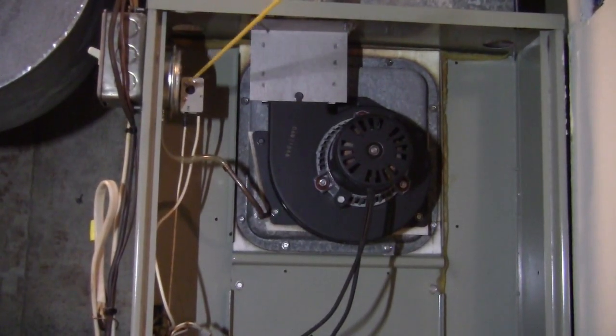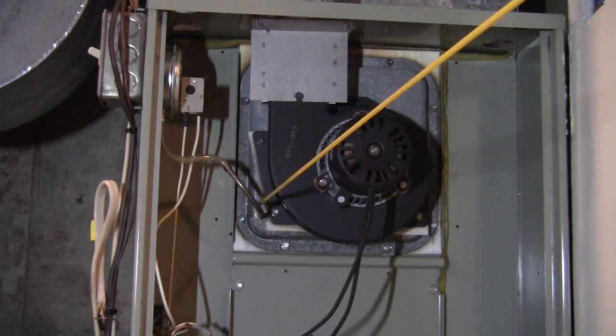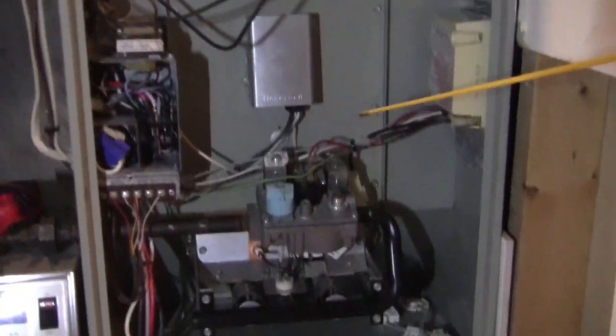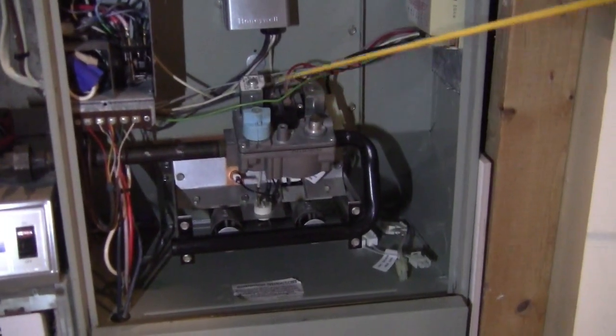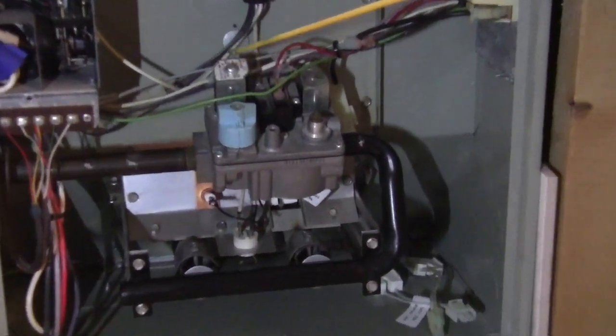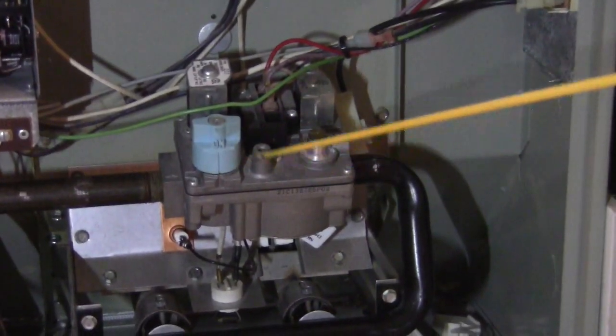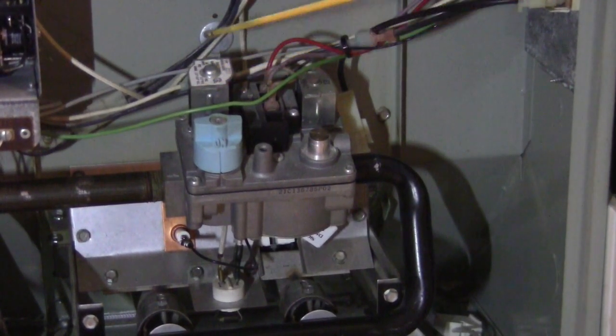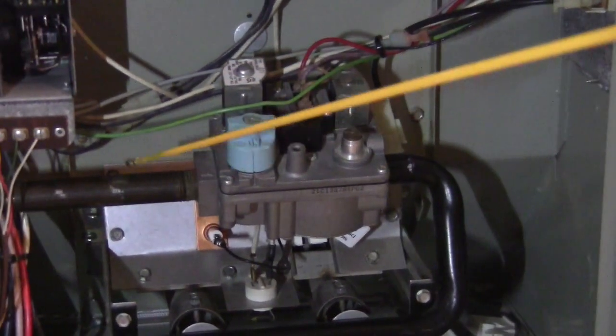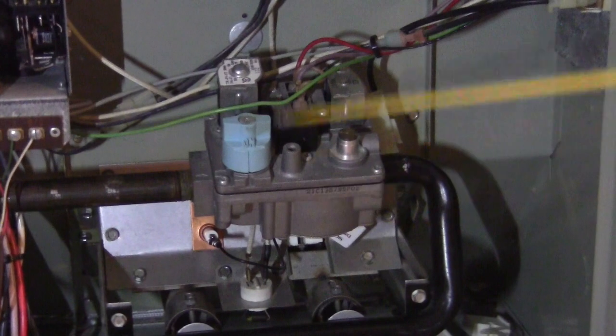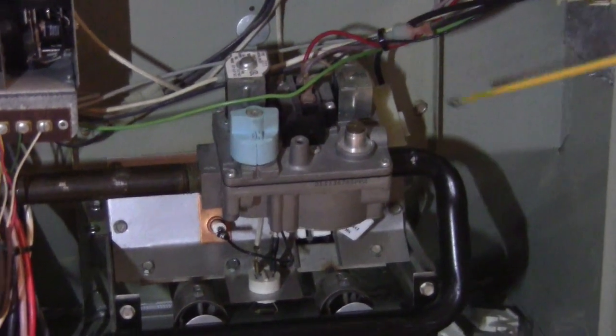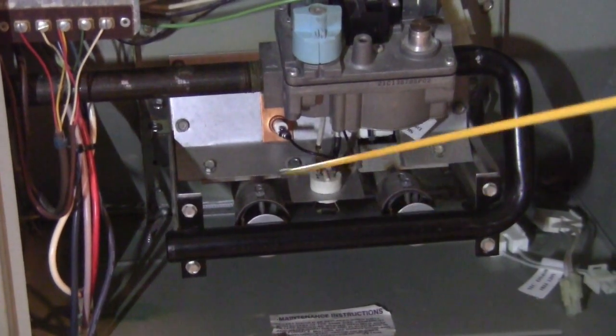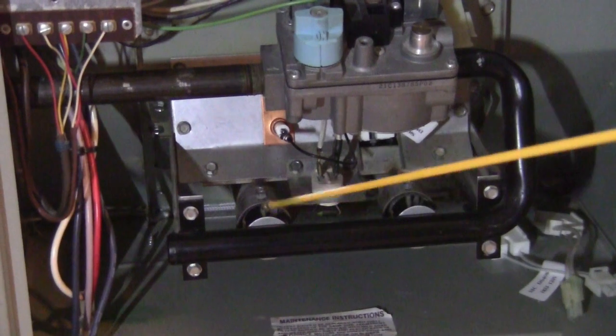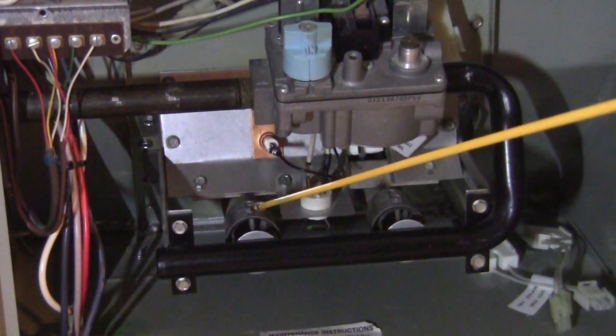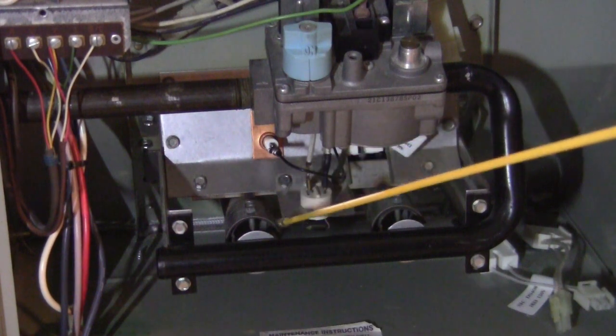After the fan runs and the vacuum sensor detects vacuum here, the controller will start to provide the signal to the valve over here. This is the gas valve. You can send the signal to the gas valve. This is the electronic relay. It's a valve that controls the gas flowing from here to the burner. So you trigger the valve, and once the valve is triggered, gas is provided from here into here. This is the major function for the burner to start to work.